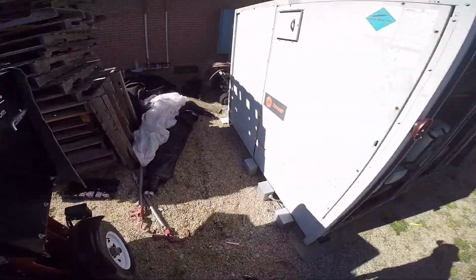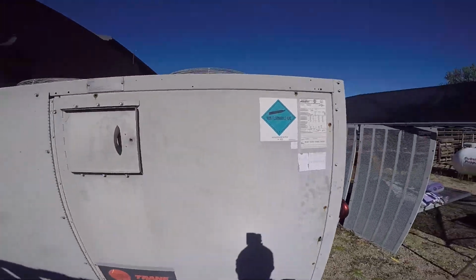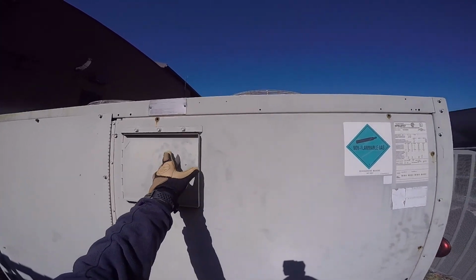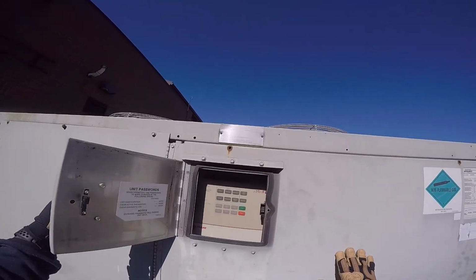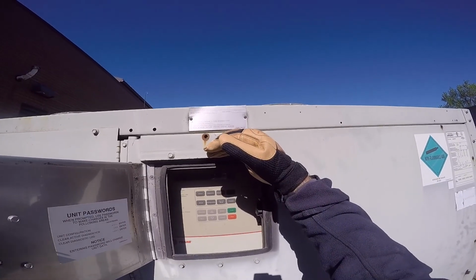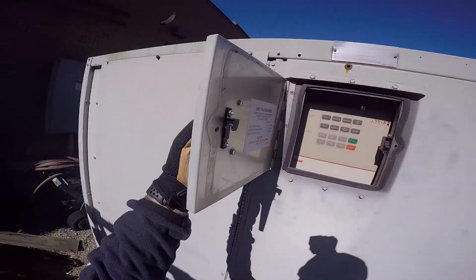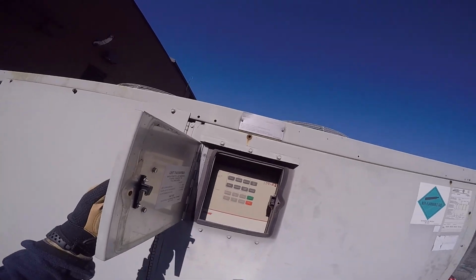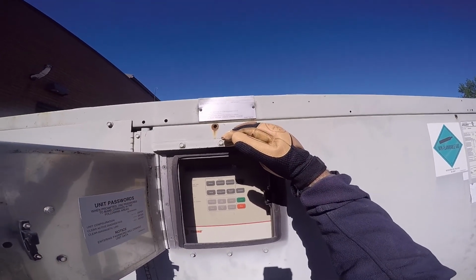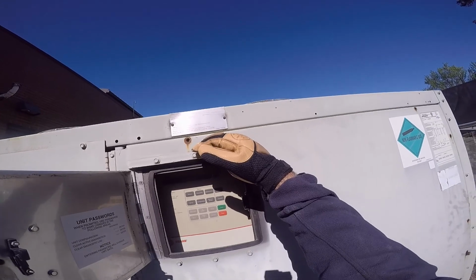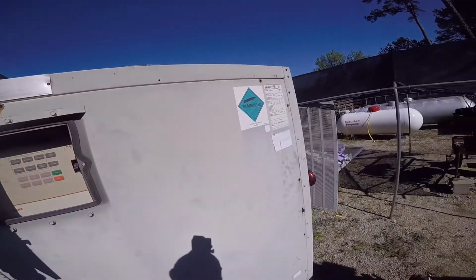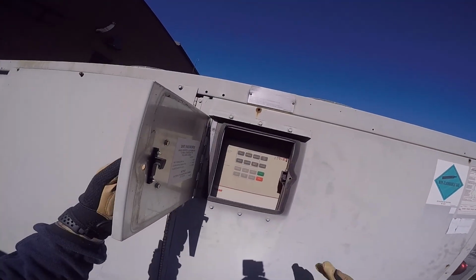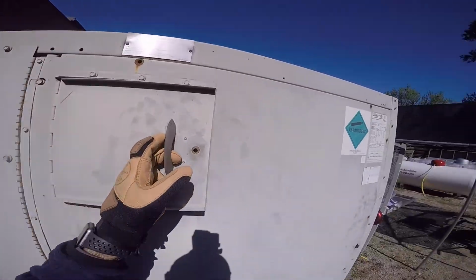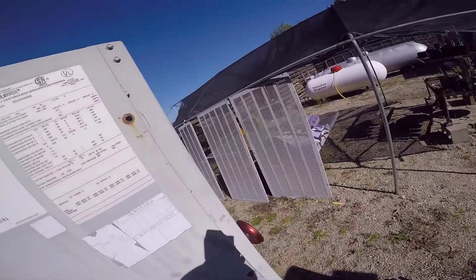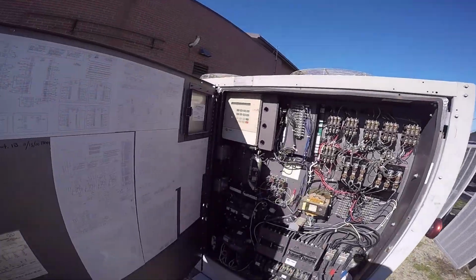So let's go over a PM. The first thing you want to do before you do anything to any chiller when you walk up is check the panel. You want to make sure there are no alarms, because if you throw the disconnect or turn the power off, you could lose your alarms. You might even lose the history and not be able to see it. Older panels don't date stamp alarms as well, and this is an older panel.